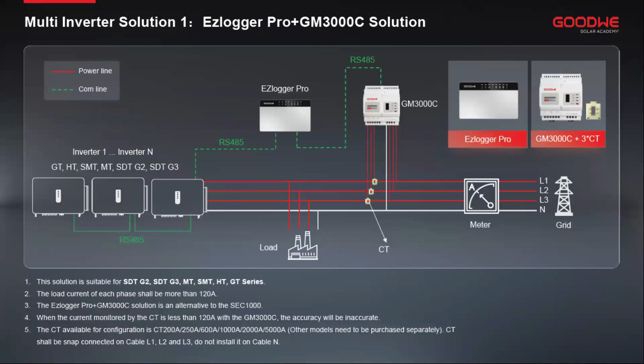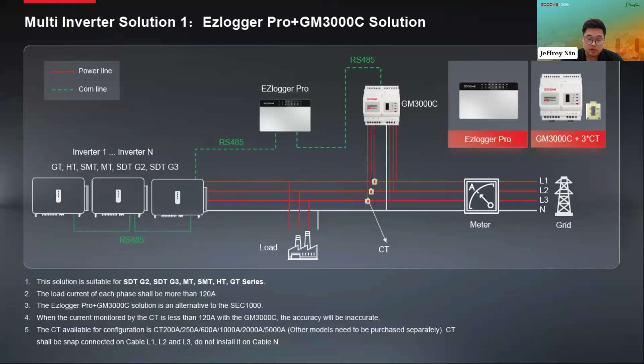For large scale C&I projects, multi-inverter power limit solution can also be used. Multi-inverters are connected in series through the RS485 interface, and the RS485 of the inverter at the near end is connected to the Ezlogger Pro. This is our data logger, which collects the value and direction of the current at the parallel point through the current transformer, which we call CT. When it detects that the parallel point sells power to the grid in a reverse direction, it will send a demand to the inverter, which makes the inverter's output power matched with the load, so as to achieve the power limit function.